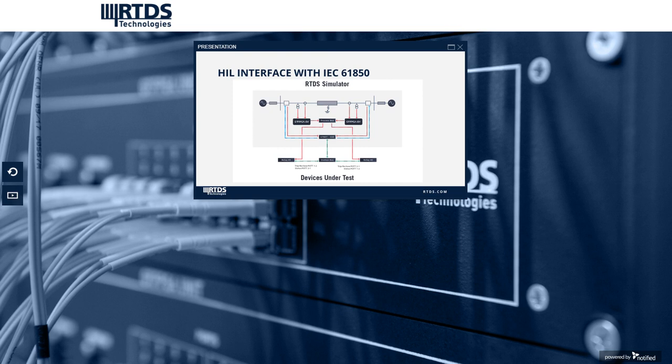With conventional I/O, we would be bringing the voltage and current signals out of the simulation via analog output. But here it's done via IEC 61850 sampled values. In this particular case that we're exploring today, this is done via the GTFPGA unit. Those voltage and current quantities are sent out via the process bus and received by the relays.